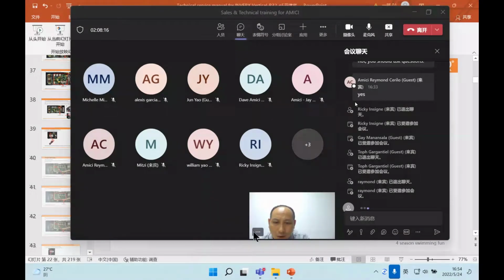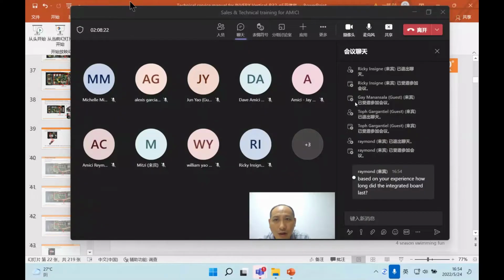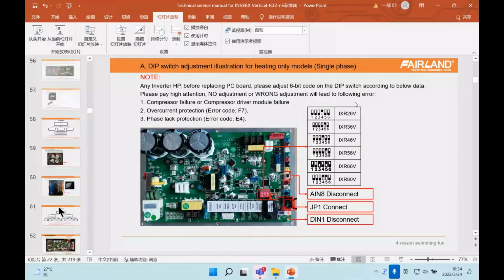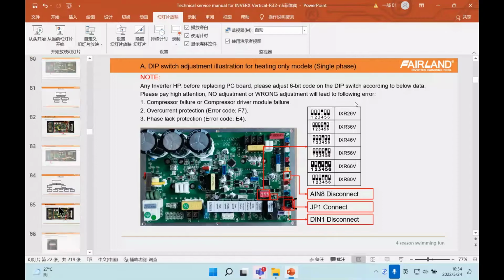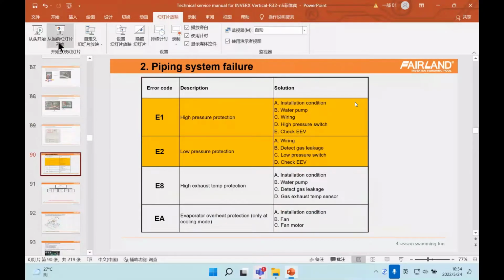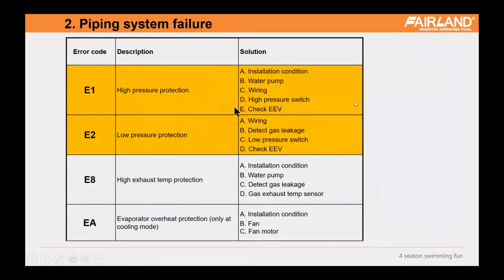So next part we will go to the refrigerant piping system. We call it the gas piping system. Just like we marked with an orange background here, E1 and E2 are the most important codes. You will see them in the future. E1 is high pressure protection. E2 is low pressure protection. E2 normally means gas leakage. E8 and EA almost never happen.